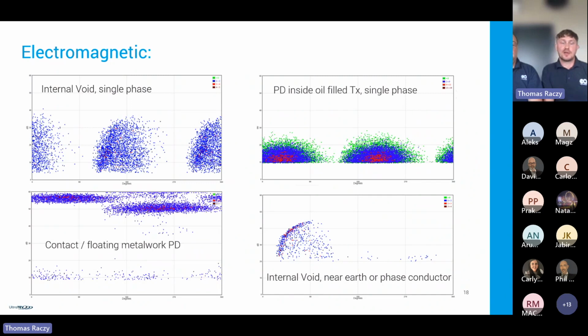Bottom left corner, a typical pattern for contact or floating metalwork discharges. Those discharges tend to be of similar amplitude with very wide inception windows. This is almost like a charging, discharging capacitor type of effect. The gap is really well defined, so those discharges always discharge across a set gap, and there's no void as such, so no aftereffects of voids. They typically end up with very similar magnitude across the power cycle and quite wide inception windows. And the fourth and last, in the bottom right corner, we've got an internal void discharge, probably in solid insulation, hard insulation, epoxy resin or pitch insulation, and there's only one group, which means the discharge probably occurs either near earth or the phase conductor.